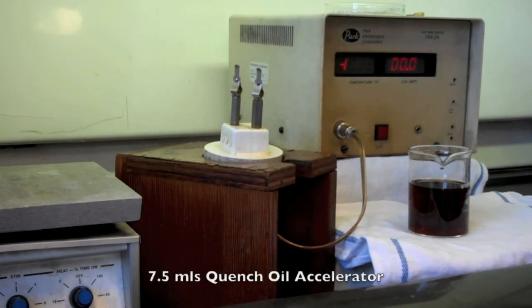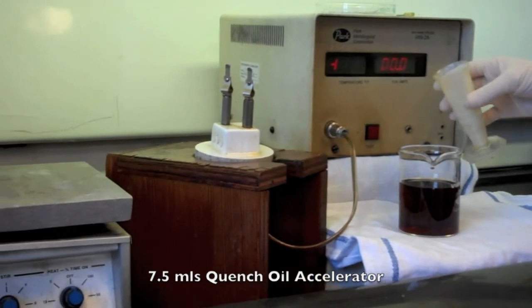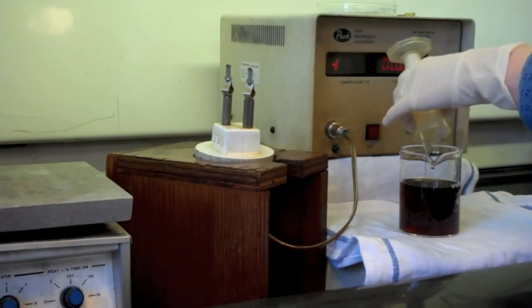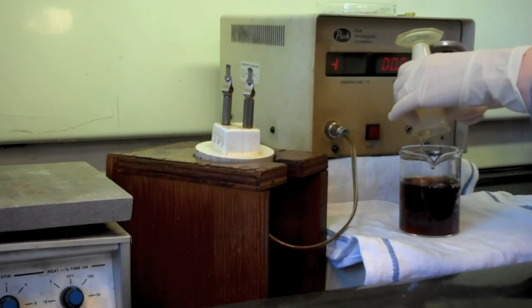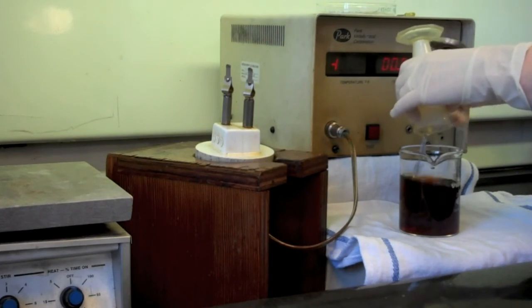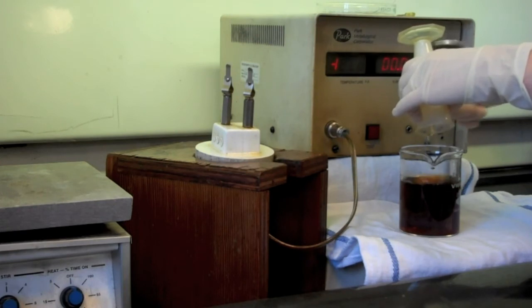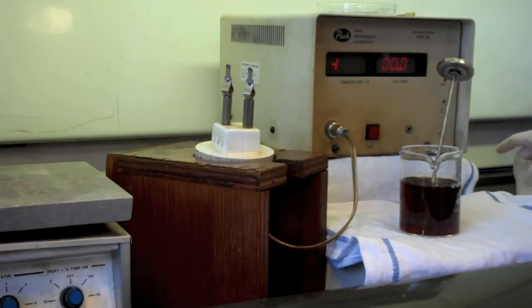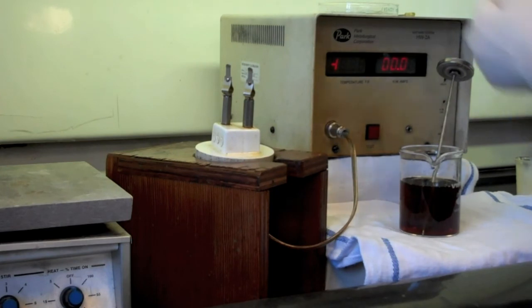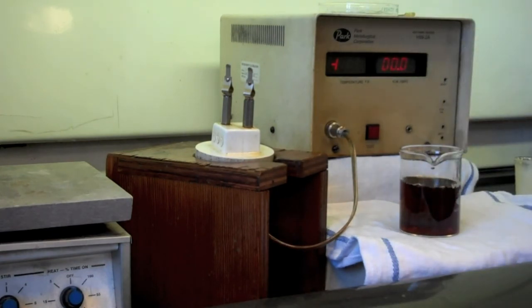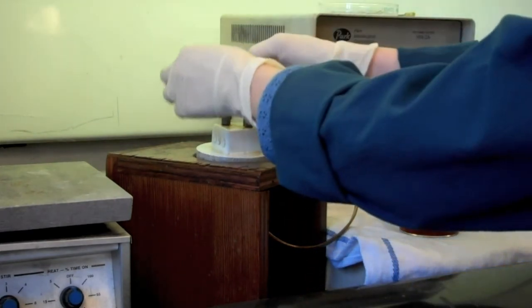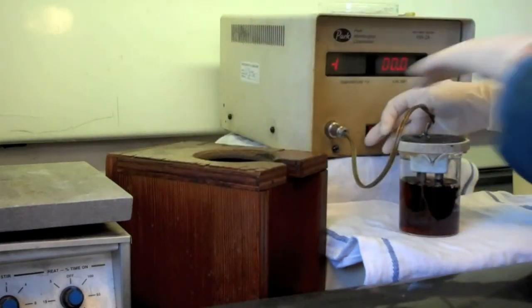I have here 7.5 mL of the quench oil accelerator. That's going into the sample, and then the test is repeated, 3 readings are taken, and the average is recorded as the hot wire of the oil. Usually adding 5% accelerator to the oil is going to bring the reading higher than 30 amps. And in that case, that's what we are going to report to the customer.